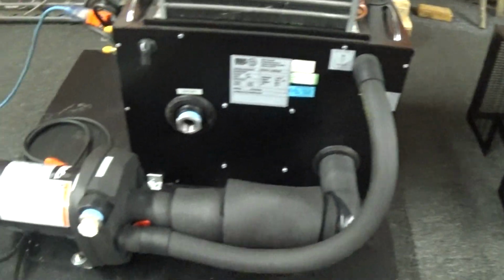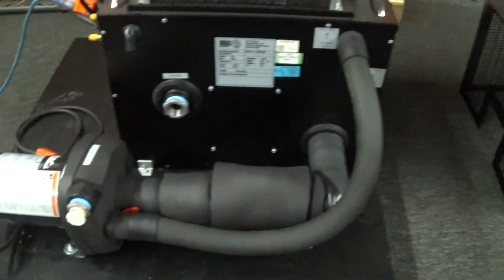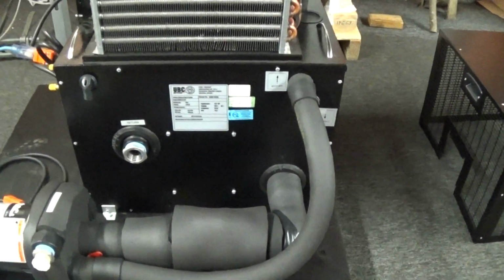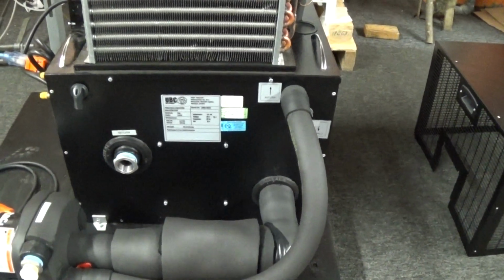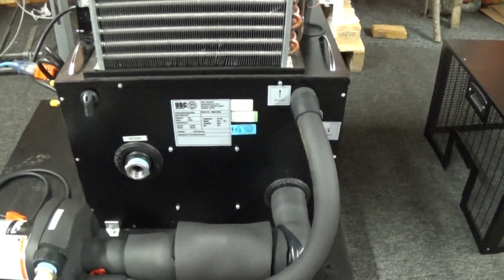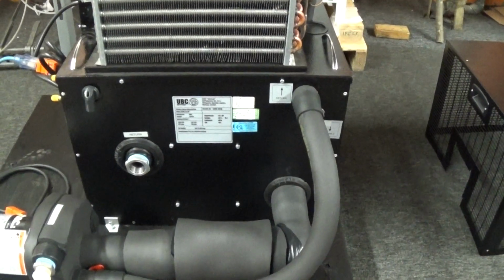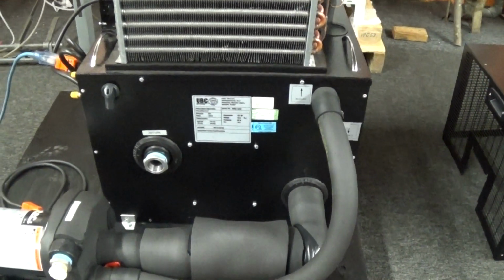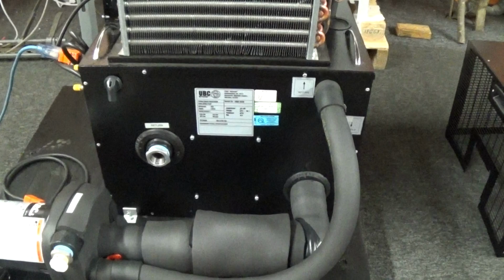That does a couple things. That prevents our pump from overheating. Then it also provides additional turbulence and flow inside the Glycol reservoir to get good heat exchange over that coil heat exchanger that's submerged in that tank.